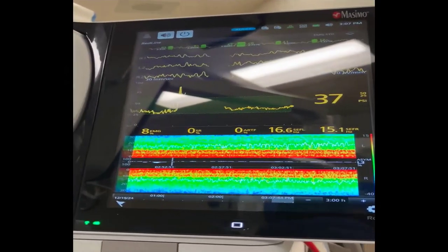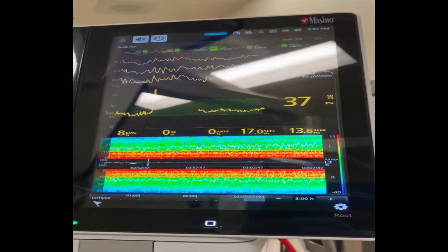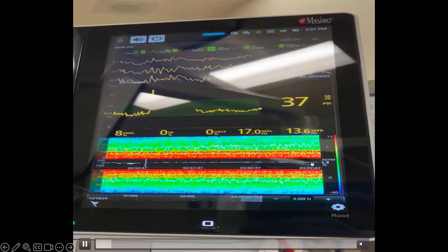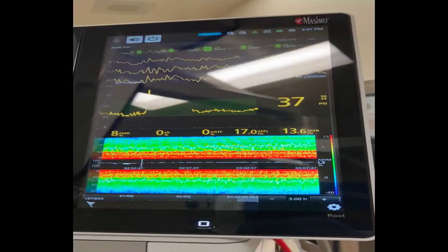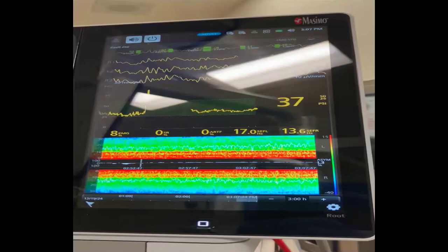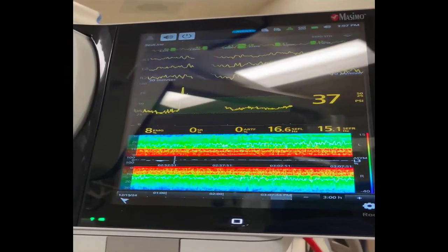The difference here, though, is that there is much more that you can analyze on a SedLine than on your BIS monitor. Also, we are seeing both hemispheres on this one, the right and the left, represented by the letters R and L, whereas on the previous monitor, we're only seeing one waveform. There are BIS monitors where you can see both, but that particular one is only showing one strip of the DSA. That's not to say it's not monitoring the patient well. It is, and you can use it quite effectively. So our patient here is adequately anesthetized.